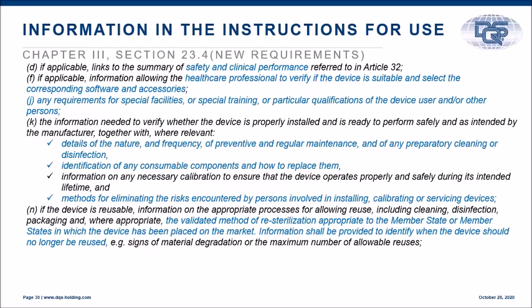And if you can recollect, there is a standard for usability, right? 62366 or 60601-1-6, which specifies that you need to define the user profile. That will include any specific training or any specific qualified personnel to operate the device. All those things were there in that standard. Now it has been brought up as a part of the regulation itself to bring it into the instructions for use.